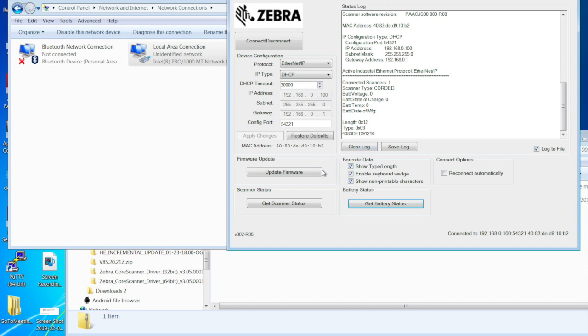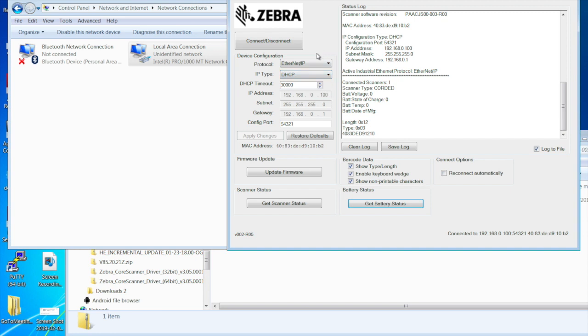This is what I do for customers that say the scanner's not working and it's not talking to my PLC. So what I generally have them do is come in here and do this, test it. And at this point, I know the scanner's connected, the EA3600 sees it, and it's talking over the network. So at this point, if I'm having connectivity issues, the issue is going to be with probably the PLC.